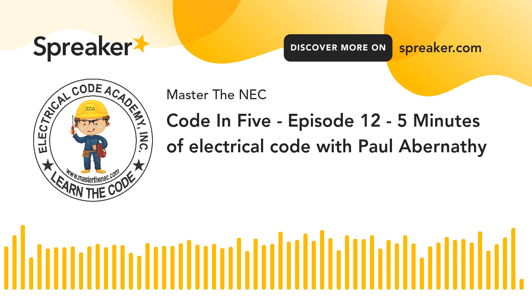So today's episode, we'll be talking about tray cable, type TC cable, and it's also found in Article 336. But what we do want to talk about before we get to the uses permitted and not permitted is that many people have been contacting me where they saw that in the 2020 edition of the NEC, under 230.43, item number 20, which is a new item to the service entrance conductors list, tray cable TC-ER was added to that list. And I'm happy to say that that is true. We did add TC-ER to that list.